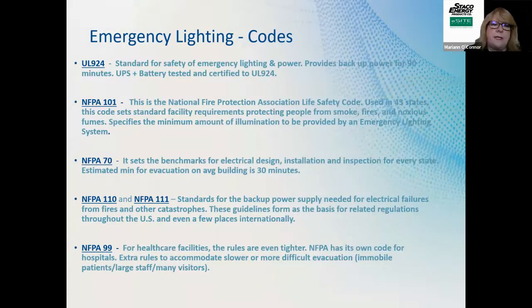I like to put up the lighting codes because I think it's important. For the UPS, we do it to the UL 924, which is the 90 minutes runtime requirement. And then you also have the National Fire Protection Life Safety Code. So the NFPA 101 looks at the minimum illumination that needs to be provided. Then you have something like the NFPA 99, which is for healthcare facilities. So those are kind of tighter controls that you need to look at. But these are just some of the pertinent codes that you'll see in those kind of emergency lighting environments and requirements. Next slide.